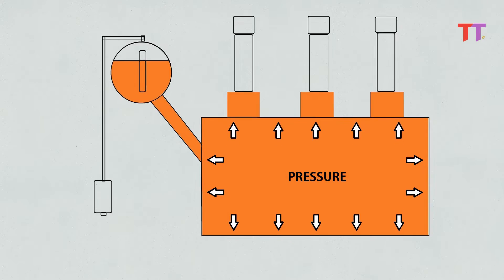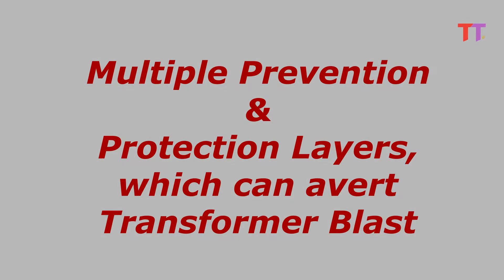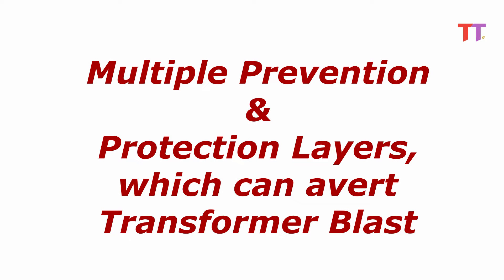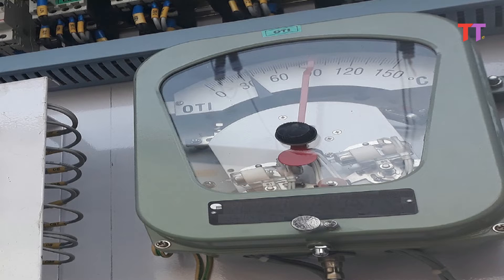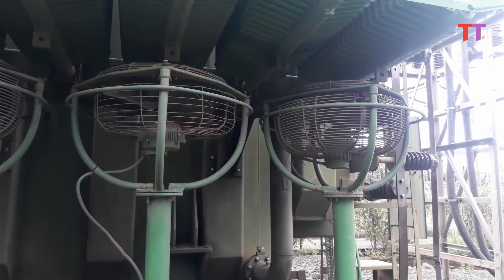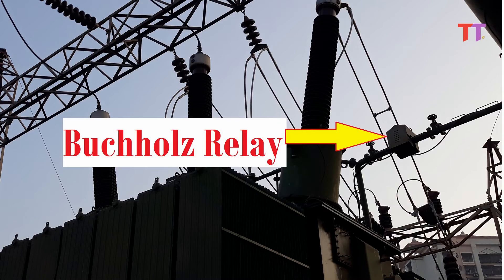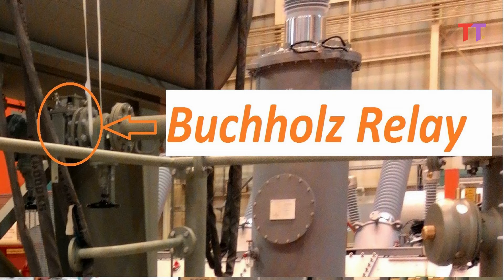Severe faults create huge pressure in a very short period of time. This pressure is so huge that it explodes the transformer. There are multiple prevention and protection layers which can avert transformer blast. Temperature rise of oil is monitored by OTI, called as oil temperature indicator. Also, an effective and functional cooling system prevents temperature rise.